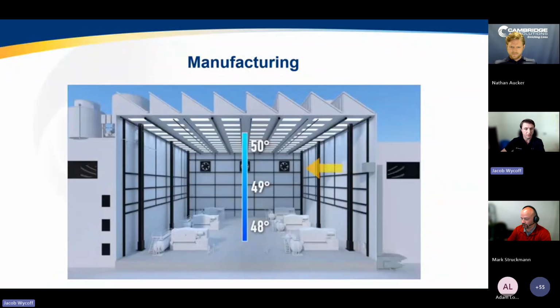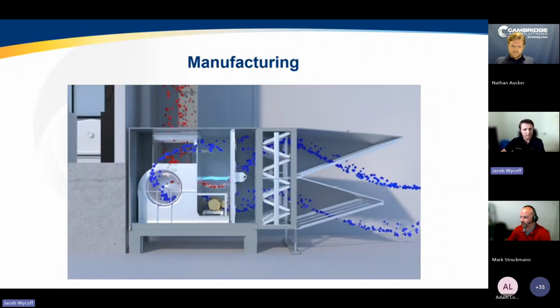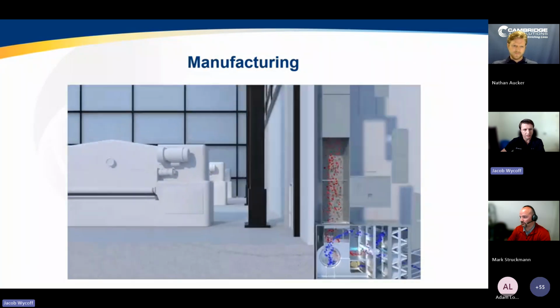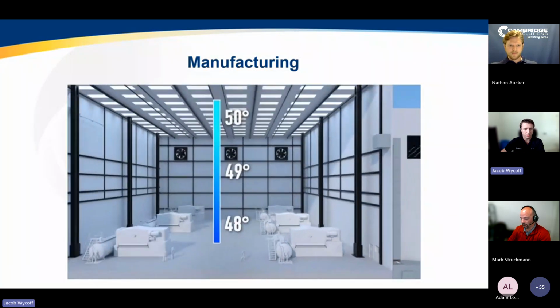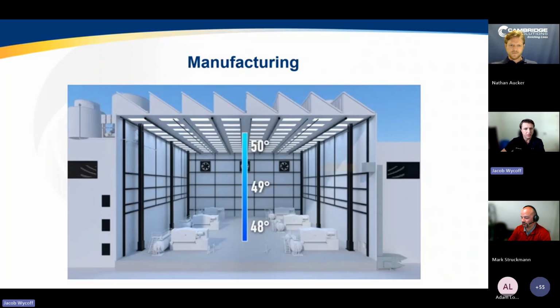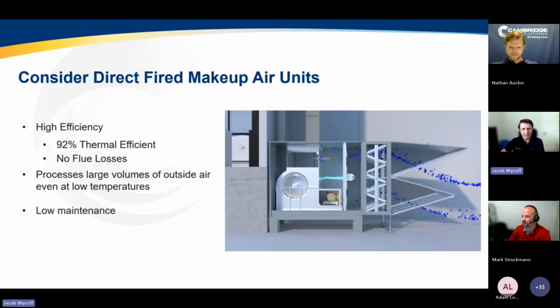And anytime, especially in a cold climate like Canada, you are exhausting air, you need to make up that air through either tempered makeup air or heated makeup air. Otherwise, you're going to get a negative room pressure that's going to be sucking in untreated cold air from the outside, which is going to cause a whole host of issues to your building. So we know we need to make up that air somehow. And we typically see direct fired makeup air units being the most effective way to provide this tempered or heated makeup air. If you work in industrial facilities quite often, you're probably already familiar with direct fired makeup air, or if you've ever worked in a kitchen type environment as well, pretty common for your kitchen type applications as well.